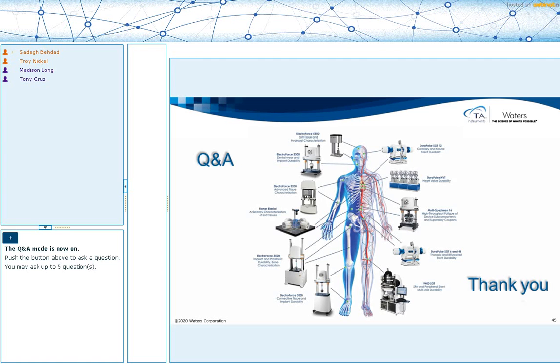And of course, that depends on your material type. In shape memory alloys, the good thing is you don't generate a lot of heat, even if you take it to higher frequencies. So that gives you additional freedom in testing those. And that is where we actually stand out, because of our direct drive motor design, we are very good at delivering higher displacements at high frequencies, and that helps you test these materials, pushing further in the frequency domain to get results fast.